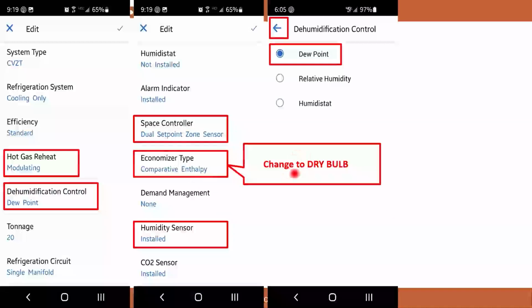I put a note in here because most of us in the Northwest are just dry bulb. We don't need all the extra humidity levels because we don't have to worry about it, nor is the building spec'd for it. So if we just change it to dry bulb, all we're going to be looking for is that discharge air sensor. Remember, switch that to conventional thermostat.